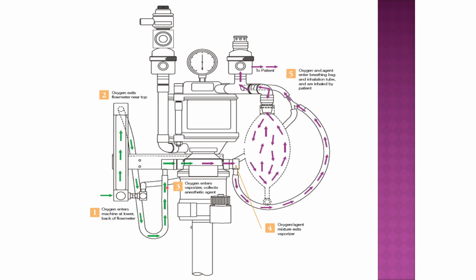You might notice a bright purple color on the top, and I'll show you that actually is a sign from the soda-sorb that the oxygen either was left on or that needle valve is leaking. Once you get through the oxygen flow meter, the next stop is going to be the vaporizer, and there's usually clues. You can look at the top of your vaporizer and oftentimes it will say inlet and outlet, or there'll be an arrow pointing which way the gas flows through there.